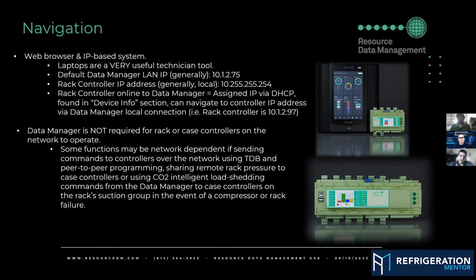Or if you have rack and case controllers on a data manager network, you can go to the device tab and then device info, and it will show you the IP address of every single controller that's on that data manager. And if you're plugging into the data manager, you can then use that IP address to get to any controller. So if your rack's on the roof, it's 100 degrees outside, you'd rather be inside in the air conditioning, you can log in to your rack controller that way. I've definitely been on that side of things before. So those of you that are new to controls, this is a lot. Talking about IPs and all these numbers here, it does take a little bit to learn.